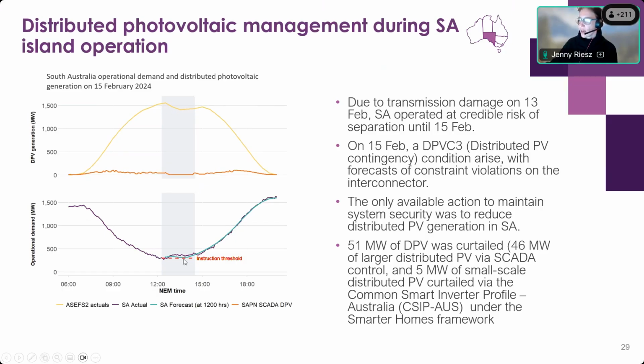Here's the threshold of demand that we asked the networks to maintain, and the actual demand that they were able to track in purple there. So it was a relatively small amount of curtailment, but required to keep us within the secure range. So the actions that were taken there was to curtail about 50 megawatts of PV.